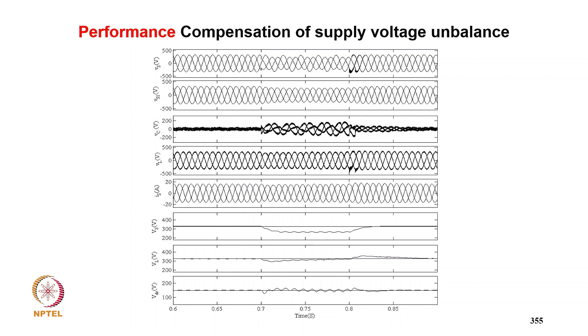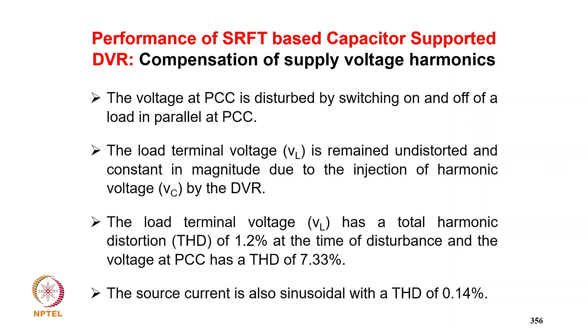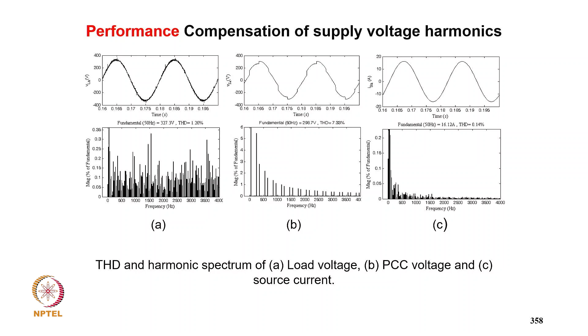Coming to compensation of supply voltage harmonics. The voltage at PCC is distorted by switching on and off a load in parallel at PCC. The load terminal voltage remains undistorted and constant in magnitude due to the injection of harmonic voltage by the DVR. The load terminal voltage has a total harmonic distortion of 1.2% at the time of disturbance, and the voltage at PCC has a THD of 7.33%. The source current has a THD of 0.14%. These show how the voltage is distorted and how the load voltage is regulated, and how the load voltage, the PCC voltage, and the source current look. So you are able to get quite a low THD of 1.2% in your load voltage.